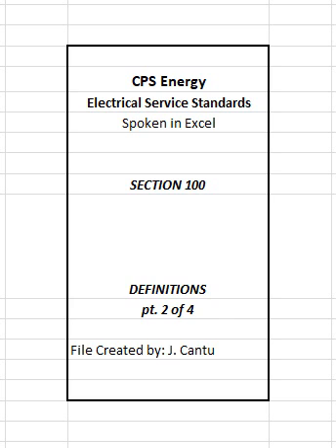Ground fault current path. An electrically conductive path from the point of a ground fault on a wiring system through normally non-current carrying conductors, equipment, or the earth to the electrical supply source. Ground fault protection. This function trips, opens, a circuit breaker or sounds an alarm in the event that there is an electrical fault between one or more of the ungrounded, phase, conductors and ground, earth. This ground fault protection function may be incorporated into a circuit breaker.